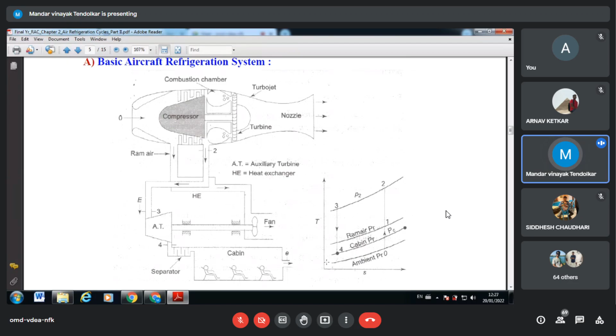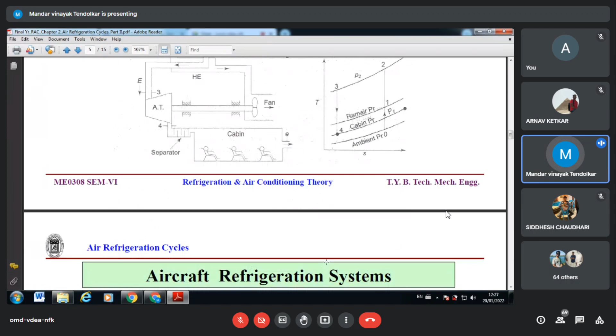After the heat rejection, then expansion, so lowest possible pressure, lowest possible temperature, and then it gets exposed to the cabin to absorb the heat, say 45 or 50 degrees Celsius, and comes back to the original condition. Why would pressure change? It's the same — 4 to E would be at the same cabin pressure, it's only sensible heat absorption, so temperature increases. This is how the cycle gets complete.